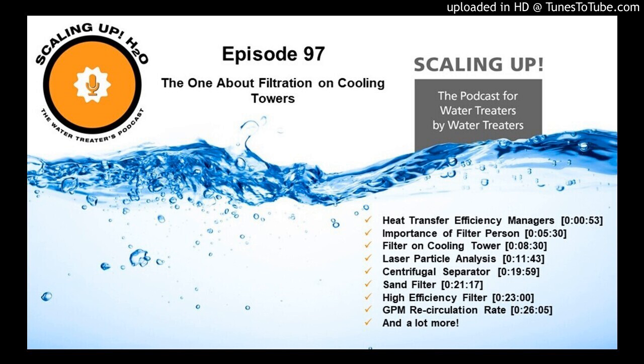Tell us about that. Well, okay, so it depends on who's buying this filter or who's working with the filtration company. If the water treater is coming on the scene after the purchase of the filtration system has been made, that's not a good plan. To me, I always recommend city water backwash. And in fact, I don't ever put a filter on a cooling tower that uses cooling tower water for backwash. It could be just locally, the places where you are have been sold by a particular filtration company that doesn't really know what they're doing. I shouldn't say it that way, but never ever use cooling tower water for backwash.